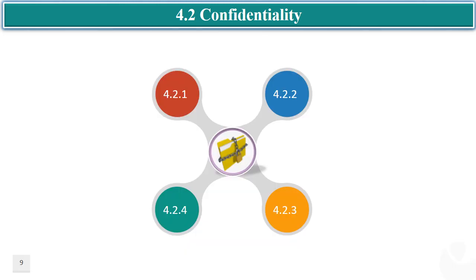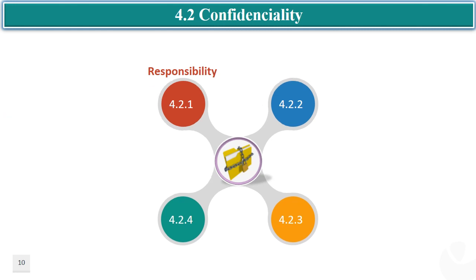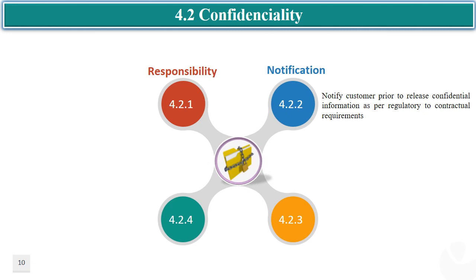Clause 4.2, which is about confidentiality, is subdivided into four sub-clauses. Sub-clause 4.2.1 states that the laboratory is legally responsible to manage all information either obtained from the customer or generated while performing laboratory activities. All customer information shall be considered as confidential. However, if the laboratory wants to share any information with others or publish it in the public domain, it shall obtain customer consent in advance. As per sub-clause 4.2.2, whenever the laboratory is required to release a customer's confidential information to legal authorities or regulatory bodies, it shall be notified to the customer, unless it is prohibited by law.